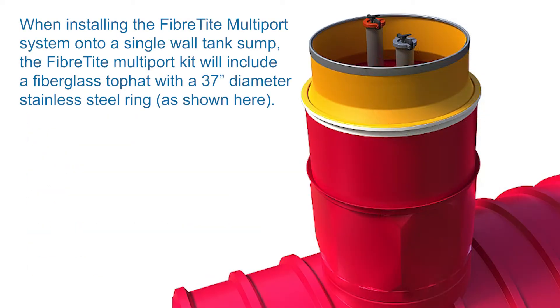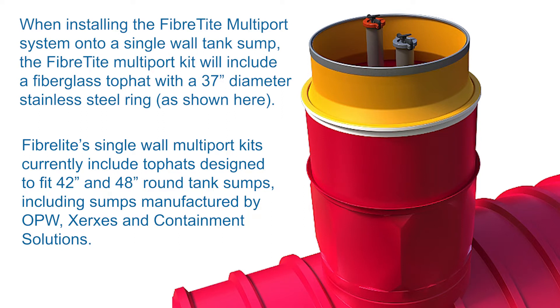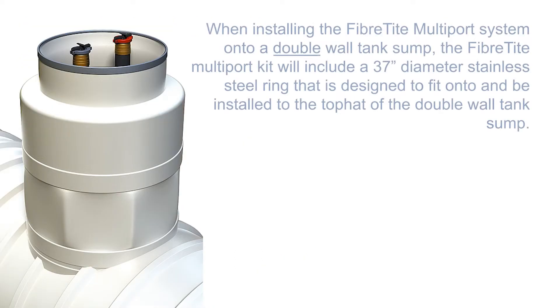When installing the FibreTite multi-port system onto a single-wall tank sump, the FibreTite multi-port kit will include a fiberglass top hat with a 37-inch diameter stainless steel ring. FibreTite single-wall multi-port kits currently include top hats designed to fit 42-inch and 48-inch round tank sumps, including sumps manufactured by OPW, Xerxes, and Containment Solutions. When installing onto a double-wall tank sump, the kit will include a 37-inch diameter stainless steel ring designed to fit onto the top hat of the double-wall tank sump.